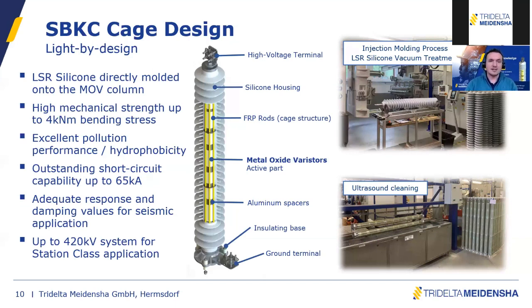So to summarize, if cost is a key factor, if you don't have mechanical strength requirements, if polymer is acceptable for you, because you know that it's not always the case. There are still companies, power utilities, using porcelain. So if you accept polymer, then we would definitely recommend going with this cage design.